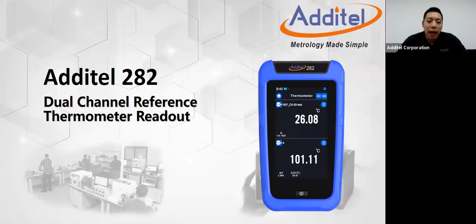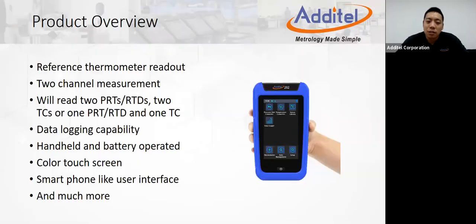So, the Additel 282 dual channel reference thermometer readout. This is a reference thermometer readout, meaning high accuracy, but customers can still use it to read any industrial PRT, RTD, or TC, no problem. It has 2-channel measurement — users can measure PRT or RTD and TC, with both channels measuring PRT or TC, or one channel PRT and one channel TC, no problem.